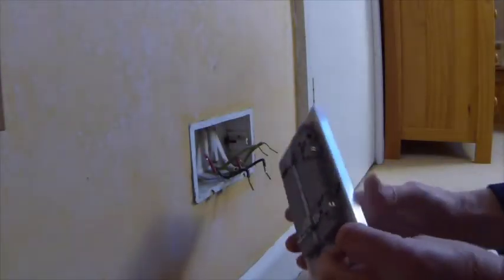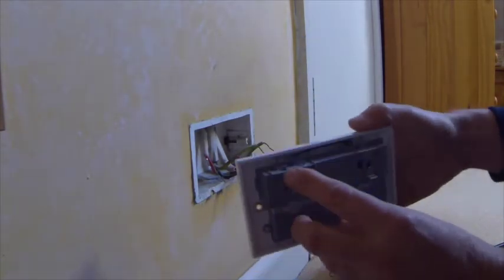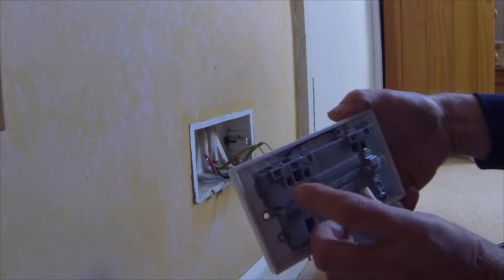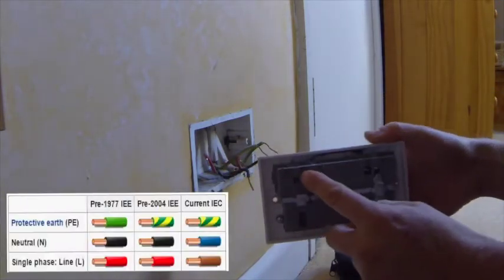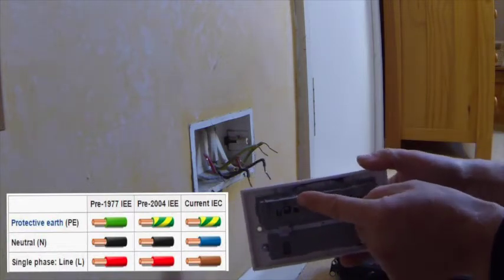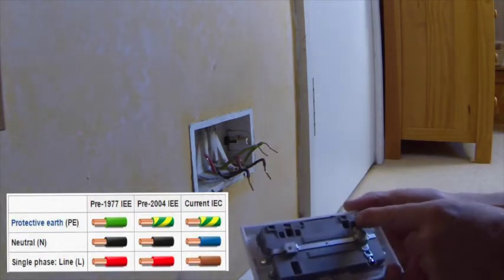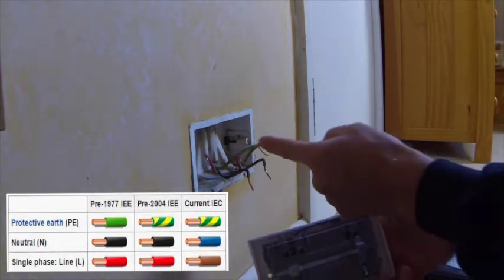They've actually color-coded the terminals on top, which is quite nice. That's brown — our old color was red, and the new color is brown for the line conductor. Neutral is blue, which in the old colors used to be black. And our earth is green and yellow, which was still green and yellow in the old colors. So we're going to wire this up in the same fashion.